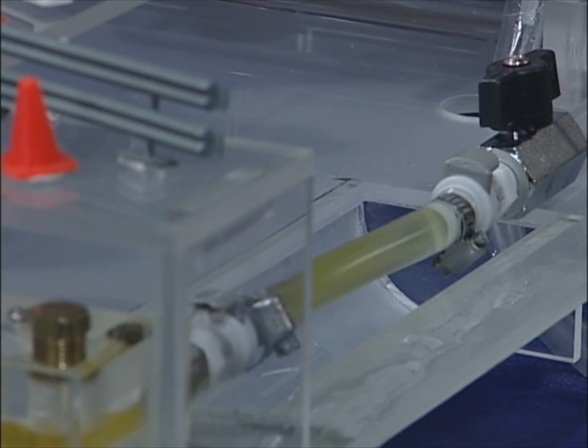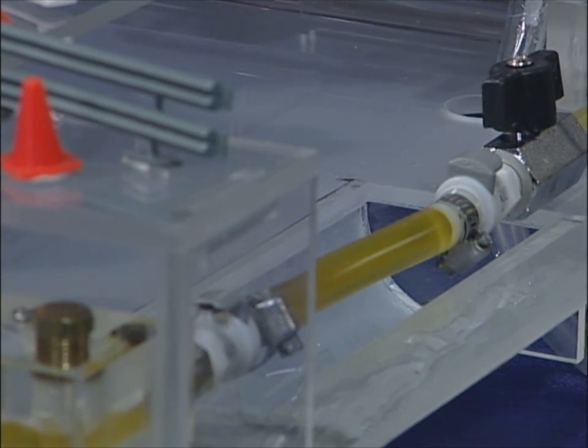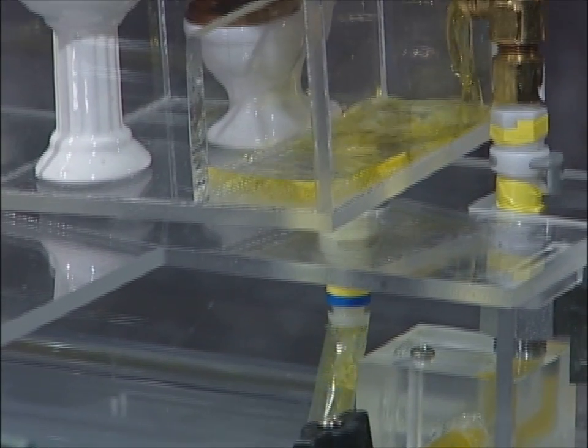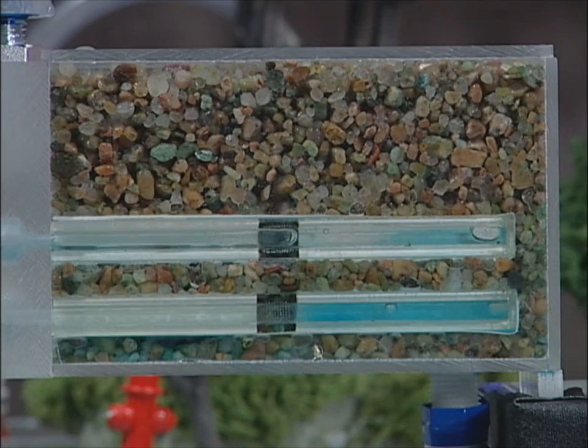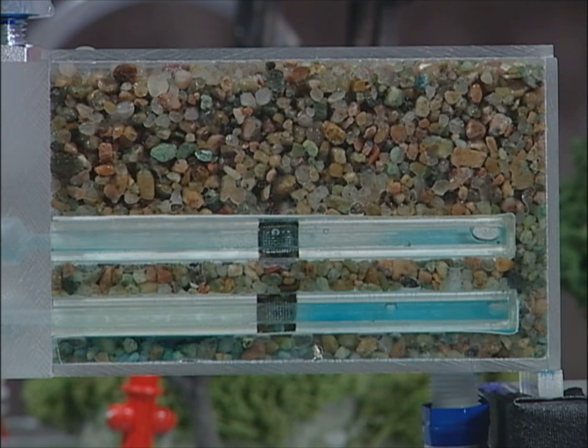Bacteria, viruses, and even chemical contamination could all be present in this tank. This contamination can now enter the system and will eventually reach households and pose a serious health threat. The fourth scenario demonstrates back siphon created from damaged water and sewage pipes. The sanitary water supply pipe is normally located a few feet above the sewage pipe, but if over time both have small cracks, problems might occur.